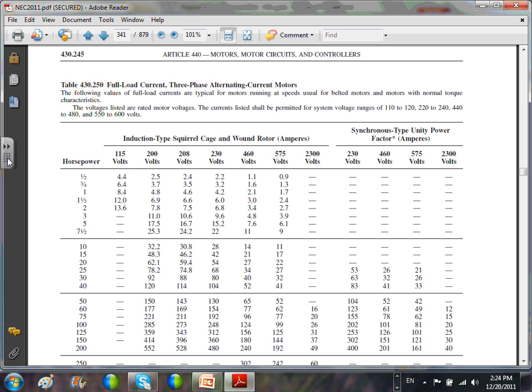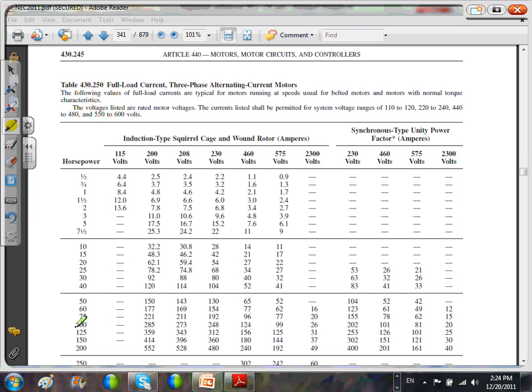Most of the systems you have probably encountered are going to be three-phase 480. So suppose that I have an air handling unit, and the air handling unit has a motor that's rated for 100 horsepower, right? A 100 horsepower motor. Most likely, if you have a motor like this, the best system for it will be 480/277. The best doesn't mean you can't run it at 208/120. Here's my 480/277. The full load for this one is right in here. So this 100 horsepower motor, based on the code, will be running 124 amps.